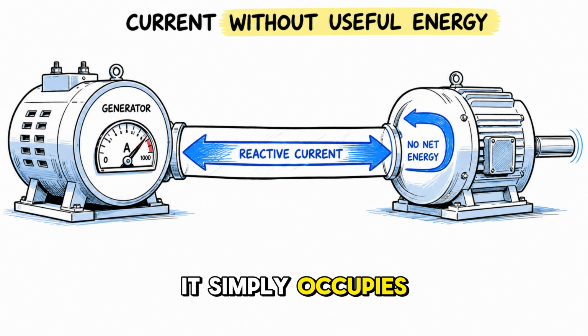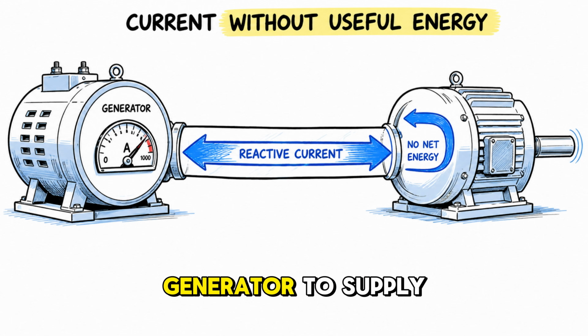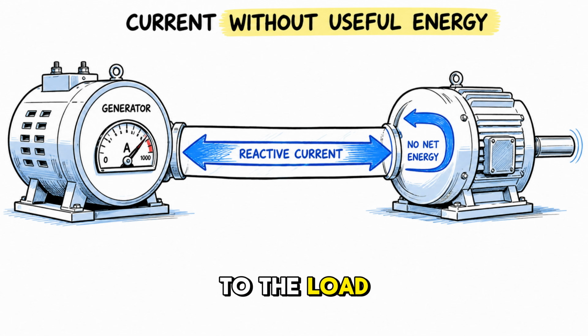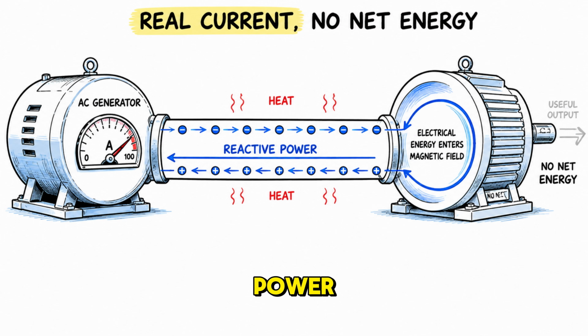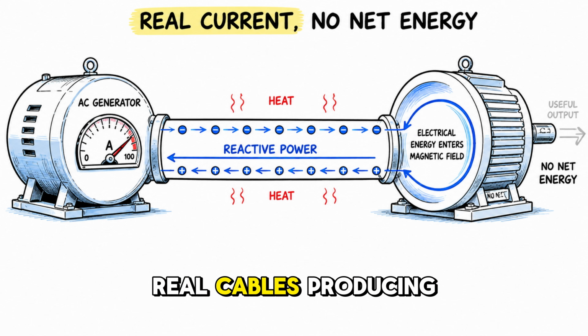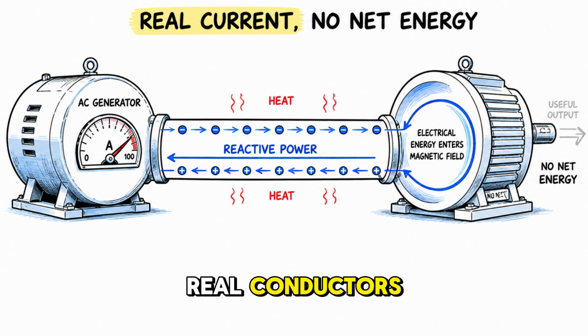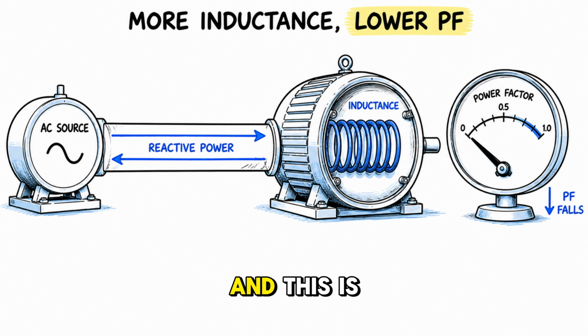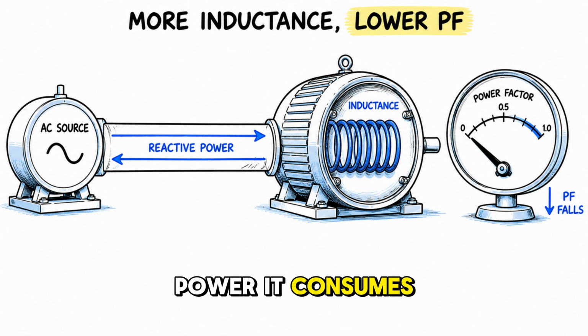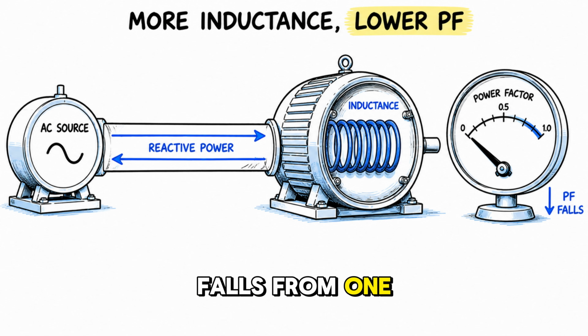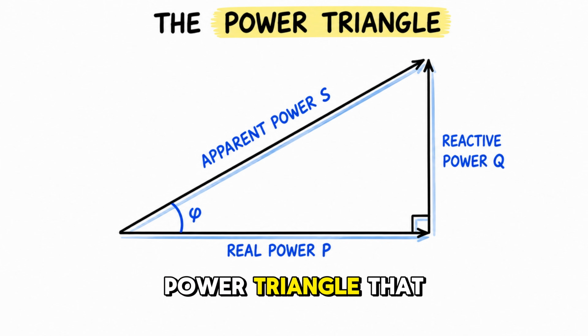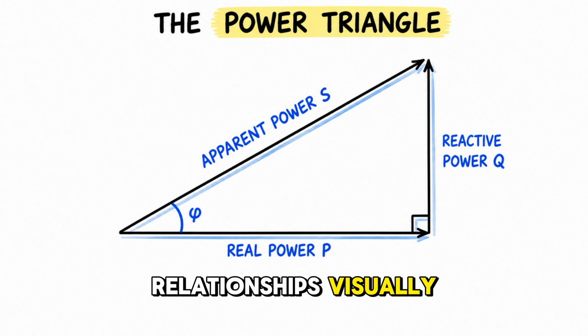It simply occupies cable capacity and forces the generator to supply current that delivers no net energy to the load. This is reactive power. It is real current flowing through real cables producing real heat in real conductors. But it delivers no net energy to the load. And this is exactly what drives power factor below 1. The more inductive a load, the more reactive power it consumes, and the further power factor falls from 1. Now let us look at the power triangle that shows these relationships visually.